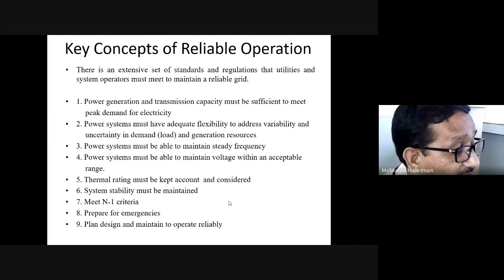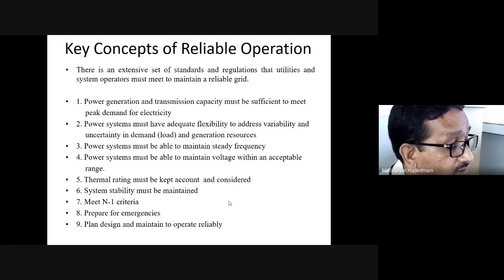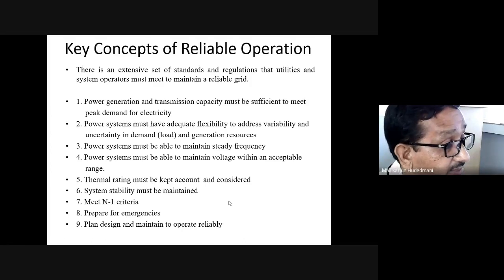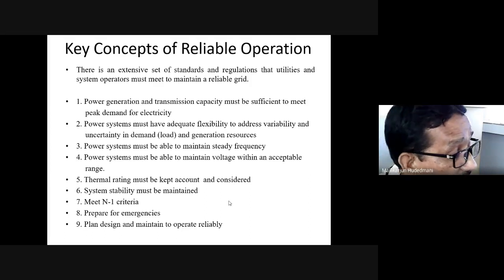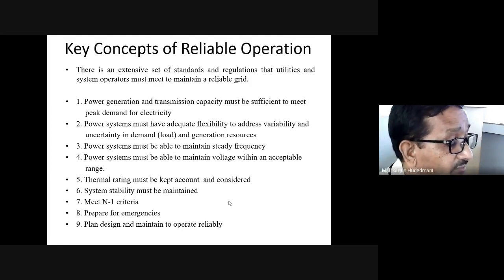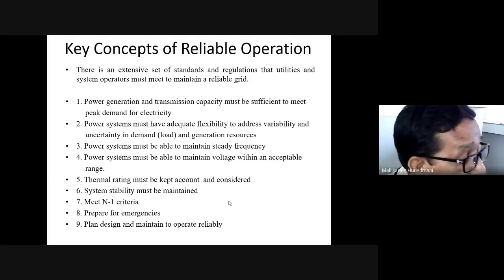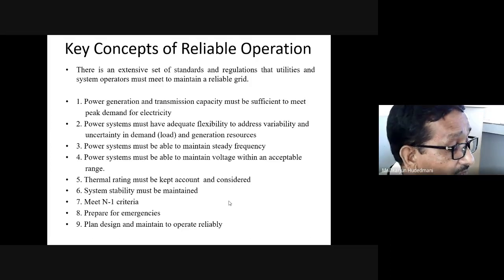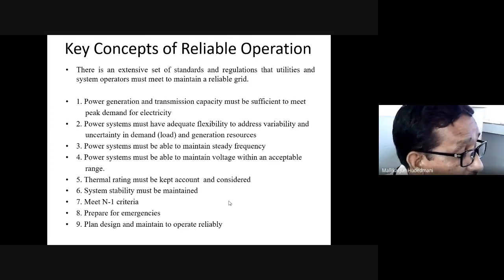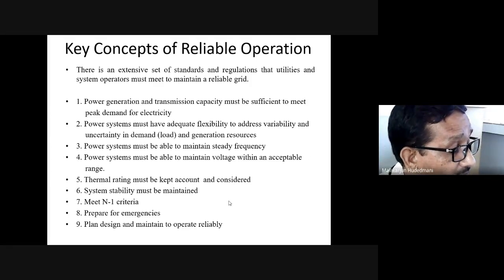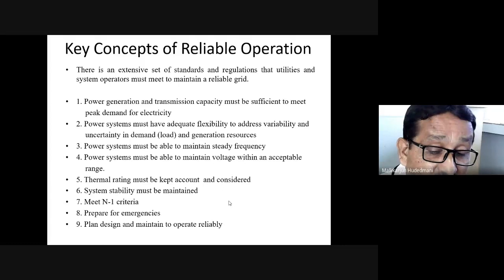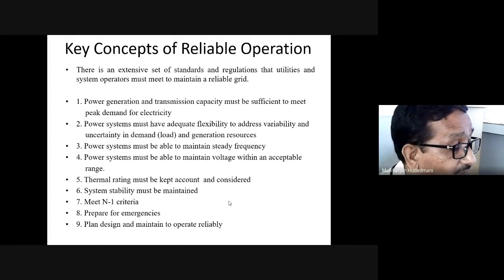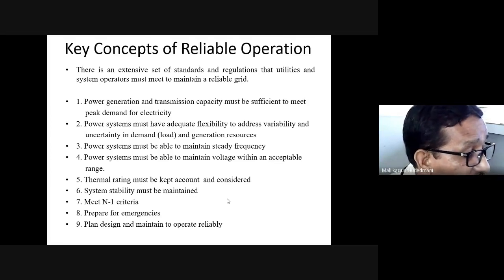The next important parameter is that system stability must be maintained. As we were discussing, stability with respect to voltage and frequency, and in terms of time scale, small, medium and large scale, and transient stability, must be there. The system must be able to cope with any contingent variation that threatens to disturb it. If that is not there inherently, the system is not going to sustain its service. In that regard, the designer has to take appropriate measures and controls such that the stability of the power system will never be challenged beyond the extent designed.